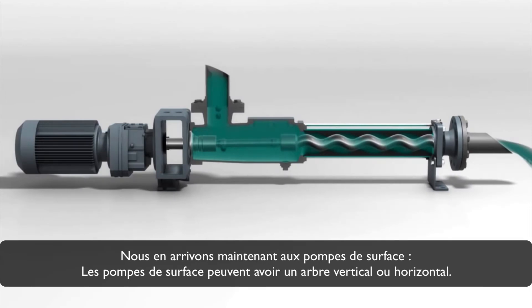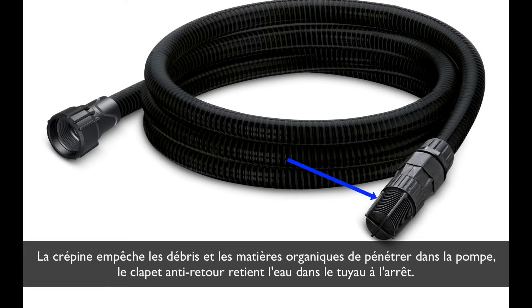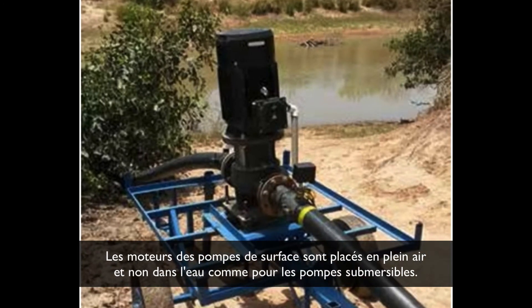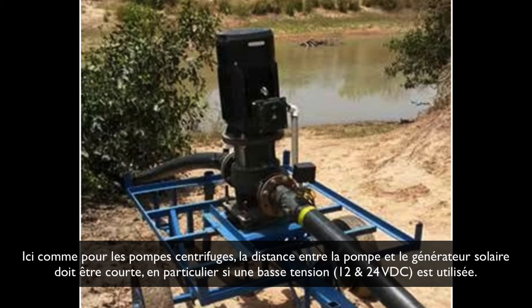Now we come to surface pumps. Surface pumps can have a vertical or horizontal shaft and they are self-priming. A strainer or sieve at the lower end of the suction hose must be used, and a check valve is an advantage. The strainer prevents debris and organic material from entering the pump during standstill. Motors for surface pumps are in the air — not in water as for submersible pumps — and have a ventilator for cooling. Otherwise, the motors can be AC or DC, and the same applies as was said for submersible pumps. The distance between pump and solar generator should be short, particularly if low voltage — 12 or 24 volt DC — is used.